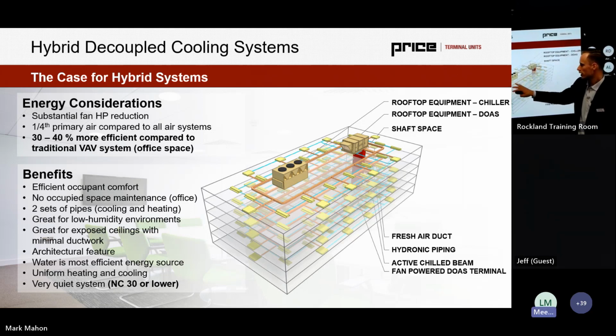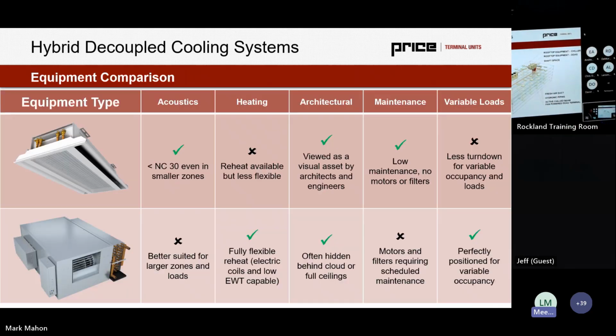But when we look at this, the case for putting them together is we get that efficient occupant comfort. We still see very low space maintenance because of the utilization of chilled beams without filters or motors. We're still seeing very low humidity environments. We have the benefits of architectural features and products that can fit behind a ceiling or in a corridor, very uniform heating and cooling. And ideally, this can be very quiet because we can handle larger products for larger zones, smaller products for smaller zones.